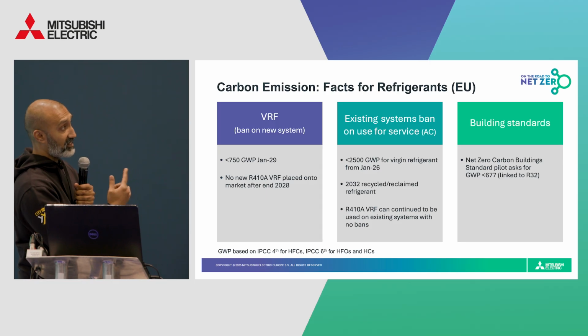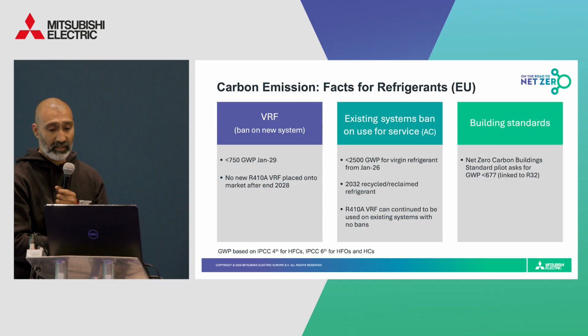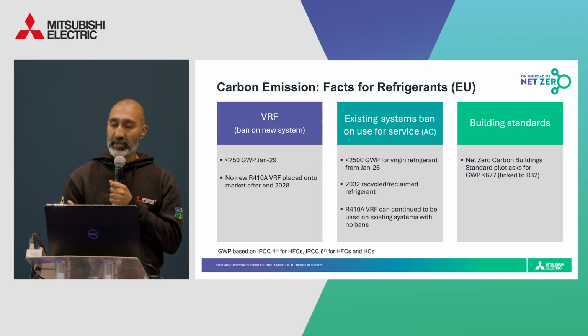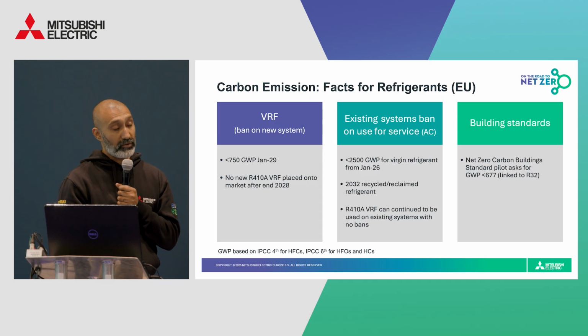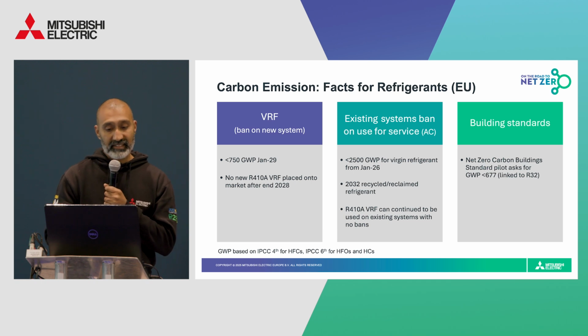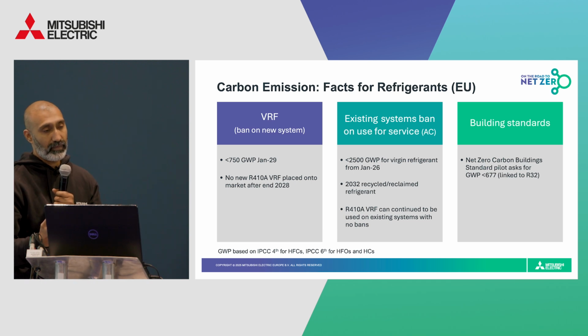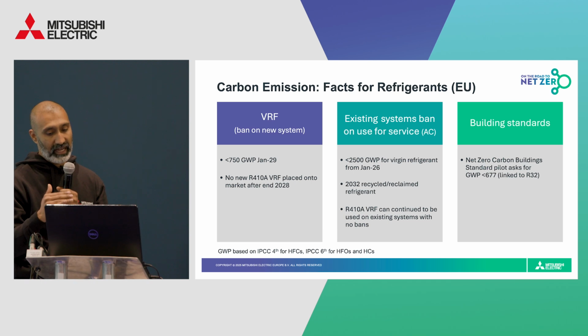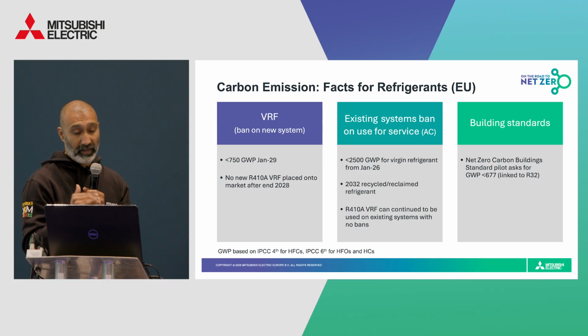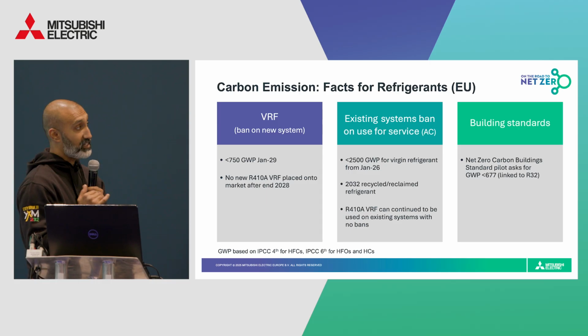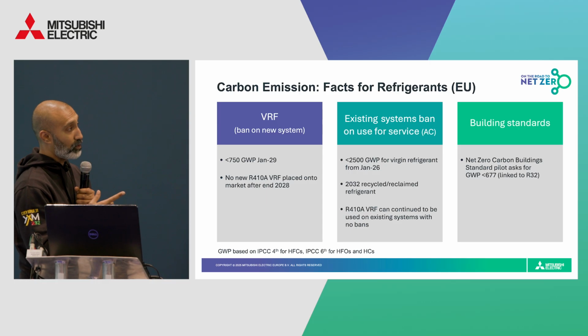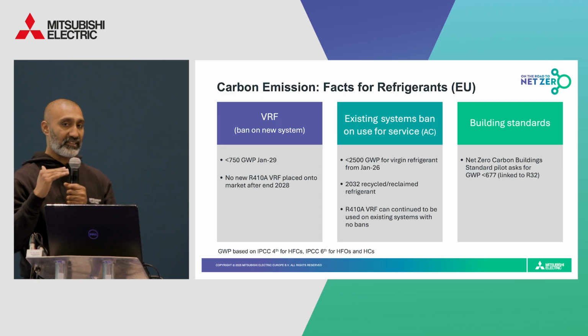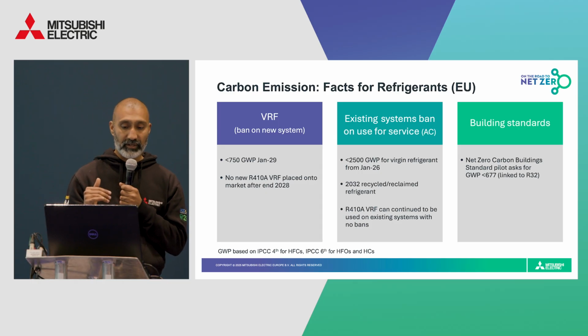So maintenance and servicing bans also come into play, and starting in 2026, new refrigerants for maintaining or servicing air conditioning and heat pump equipment must also have a GWP below 2,500, and from 2032, even reclaimed or recycled refrigerant must also be below 2,500.